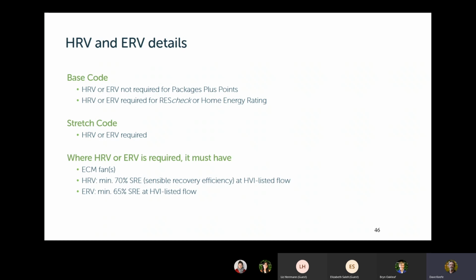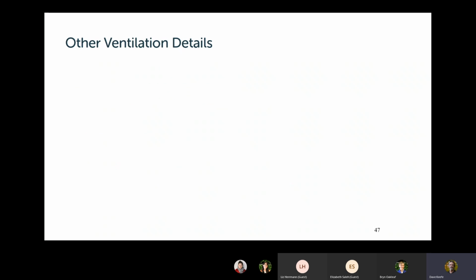And if you're doing balanced ventilation, or more accurately, if balanced ventilation is required, you must have ECM fans, and for an HRV, a heat recovery ventilator, you have to have minimum 70% sensible heat recovery. And for an ERV, an energy recovery ventilator, you have to have a minimum 65% sensible recovery efficiency. A couple other things on ventilation.